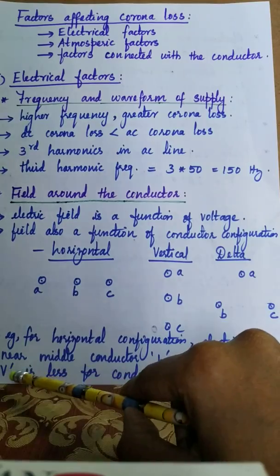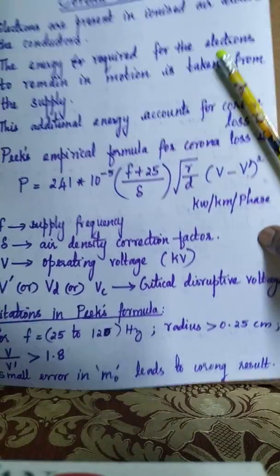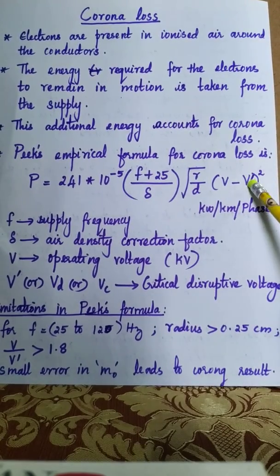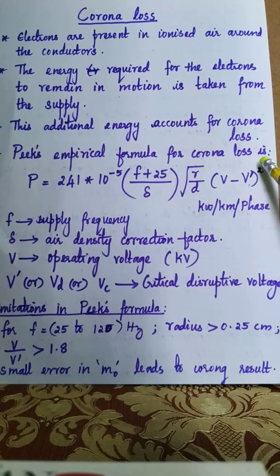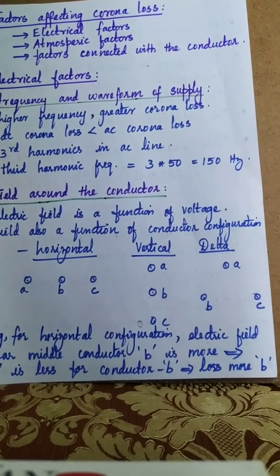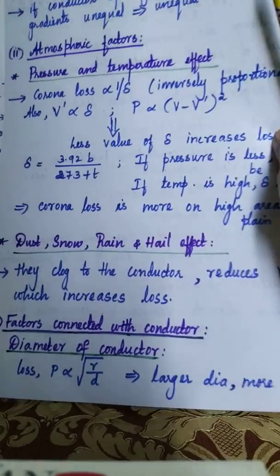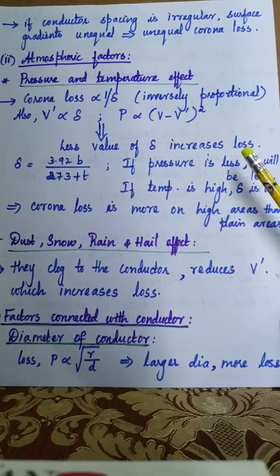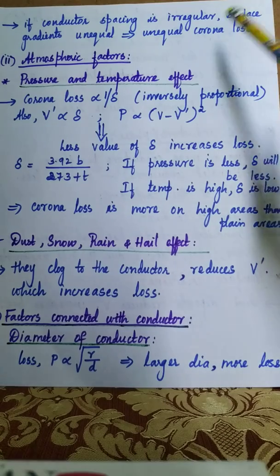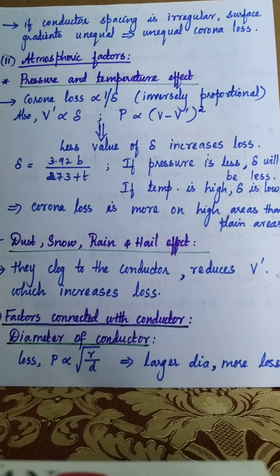If V' is less, power loss is more on conductor B, because power loss is proportional to (V − V')². With smaller V', the term (V − V')² increases, which increases the loss on the middle conductor B. Also, if conductor spacing is irregular, the corona loss occurring on various conductors will be unequal, because lesser spacing causes higher potential gradient, resulting in unequal potential gradients at the conductor surfaces and hence unequal corona loss.